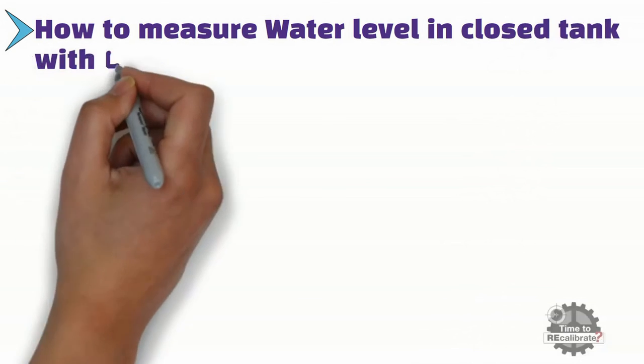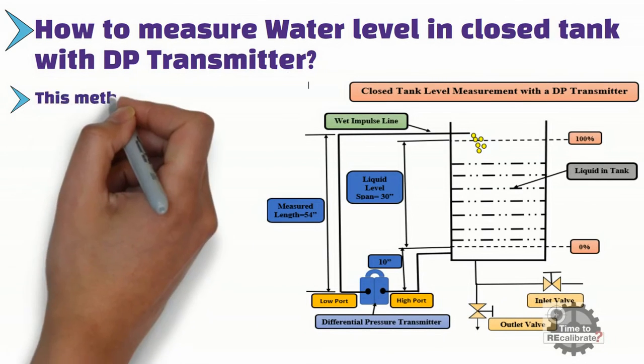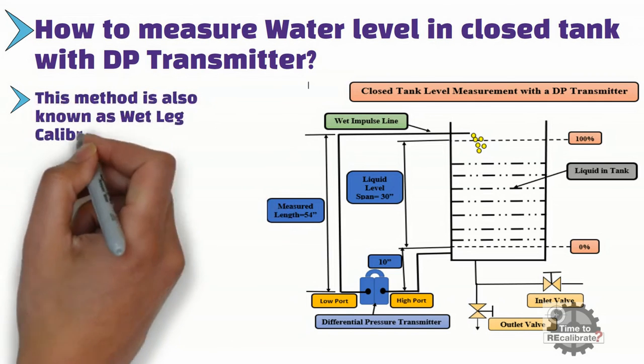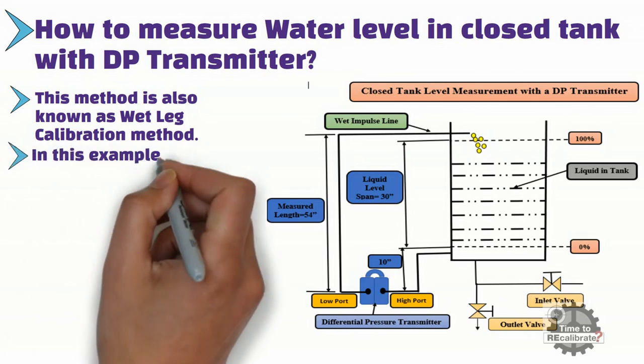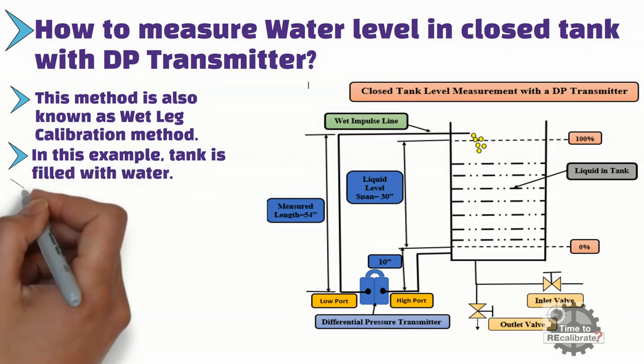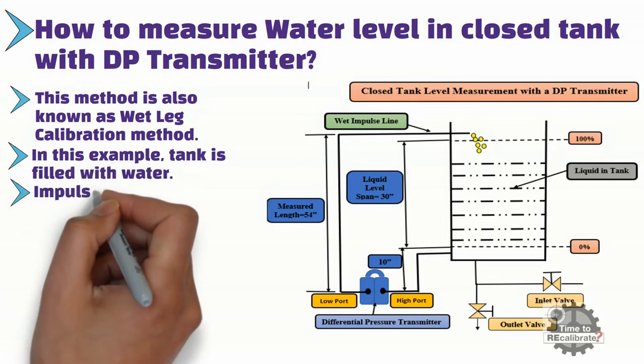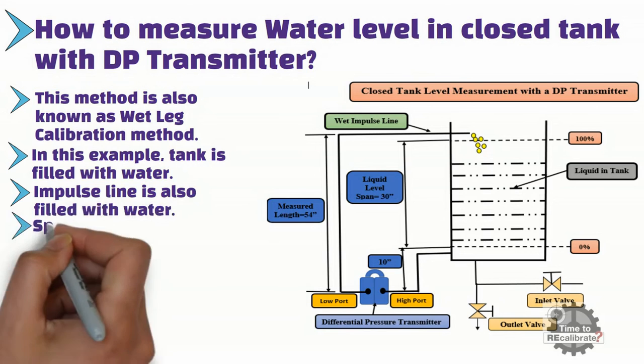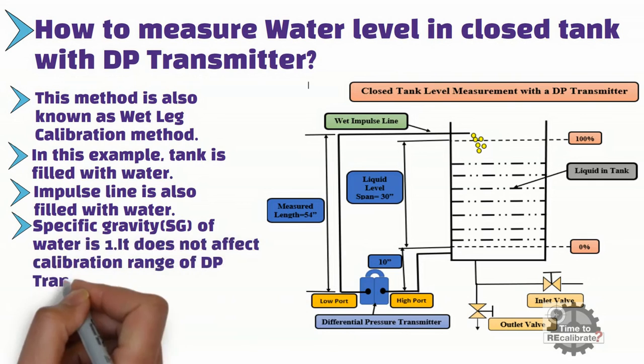How to measure water level in a closed tank with a differential pressure transmitter? This method of level measurement is also known as the wet leg calibration method. The specific gravity of process fluids plays a crucial role in calculation of the calibration range for a DP transmitter. In this example, let's assume that the tank is filled with water and the impulse line is also filled with water. Since the specific gravity of water is 1, it does not affect the calibration range.